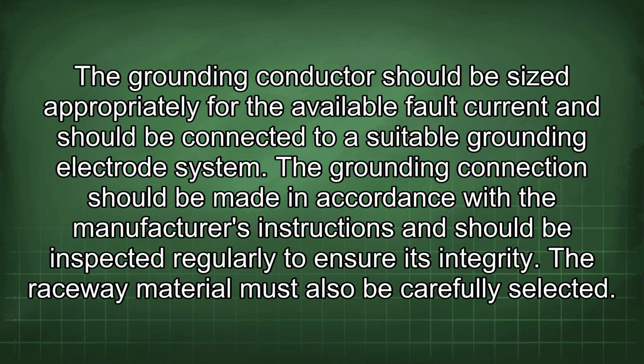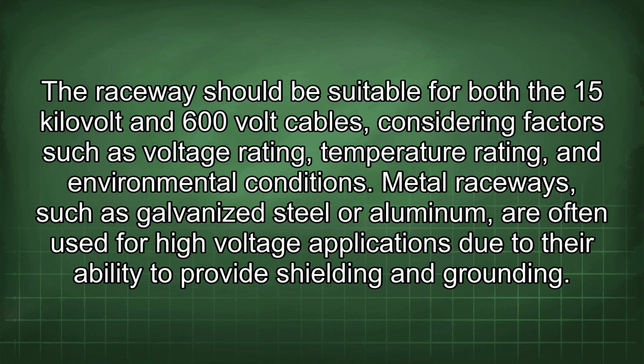The grounding conductor should be sized appropriately for the available fault current and should be connected to a suitable grounding electrode system. The grounding connection should be made in accordance with the manufacturer's instructions and should be inspected regularly to ensure its integrity. The raceway material must also be carefully selected. The raceway should be suitable for both the 15 kV and 600 volt cables, considering factors such as voltage rating, temperature rating, and environmental conditions.